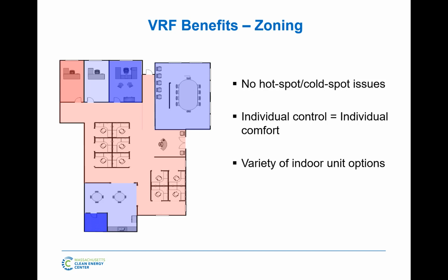A big open area, that's where alternative equipment that can do 50 tons, 100 tons at once might make more sense. So whenever you see zoning, whenever somebody says, oh yeah, we have these big rooftops, I've got 3 big rooftops, but I want to start zoning this building, they're going to have to go with VAV, with reheat and controls. That's where you say, oh, maybe VRF might make sense. If somebody says I've got 3 big rooftops and I'm happy with 1 thermostat for the whole floor of my building, and I just want to replace it, you're going to say, sure, go ahead and replace the rooftop. Because if you're not looking to zone it, VRF becomes quite an expensive way of doing that. So VRF is a zoning system.